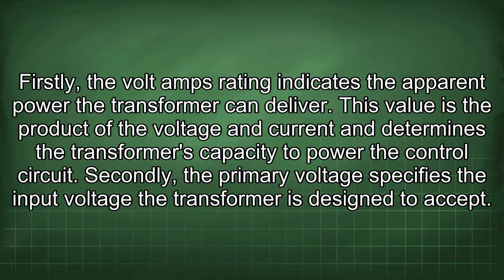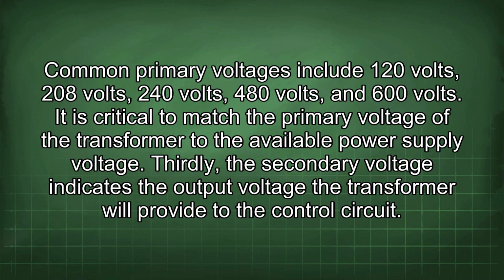Secondly, the primary voltage specifies the input voltage the transformer is designed to accept. Common primary voltages include 120 volts, 208 volts, 240 volts, 480 volts, and 600 volts. It is critical to match the primary voltage of the transformer to the available power supply voltage.